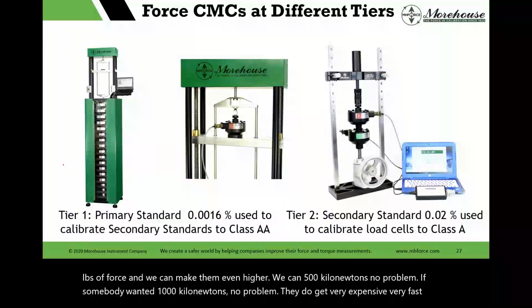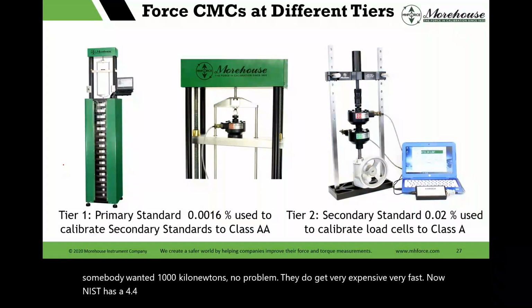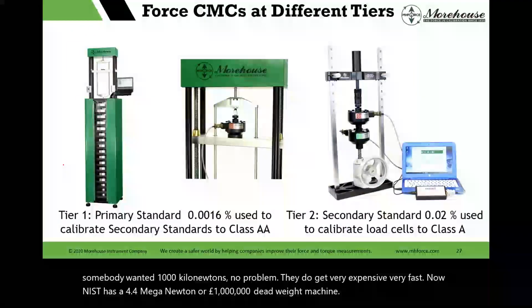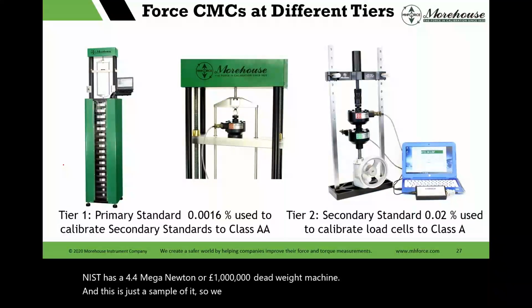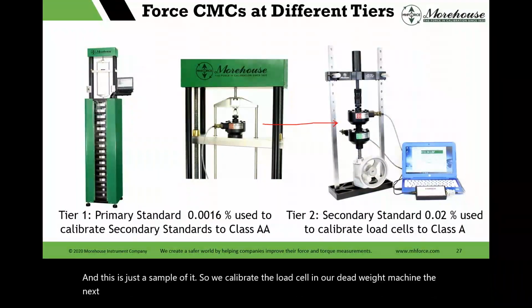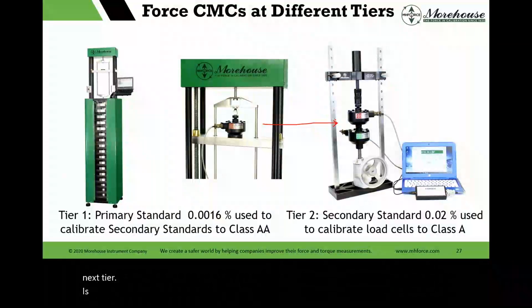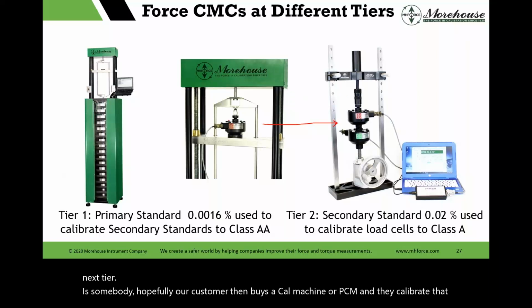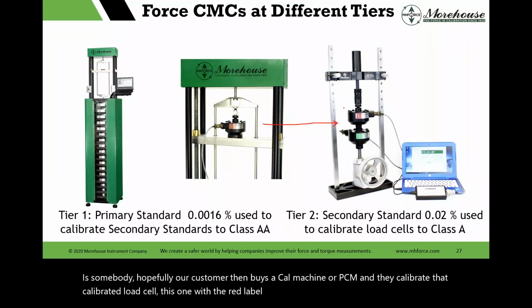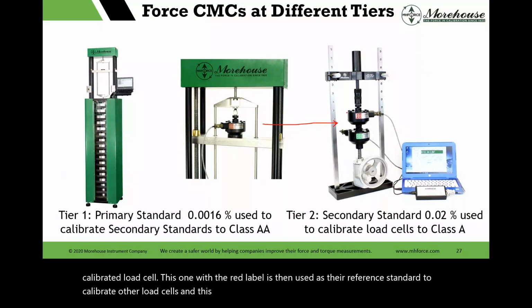Now, NIST has a 4.4 meganewton or million-pound deadweight machine, and this is just a sample of it. So we calibrate the load cell in our deadweight machine. The next tier is somebody, hopefully our customer, then buys a cal machine or PCM, and they calibrate that load cell, this one with the red label, which is then used as their reference standard to calibrate other load cells. And this is where they're typically getting the 0.2 to 0.4.